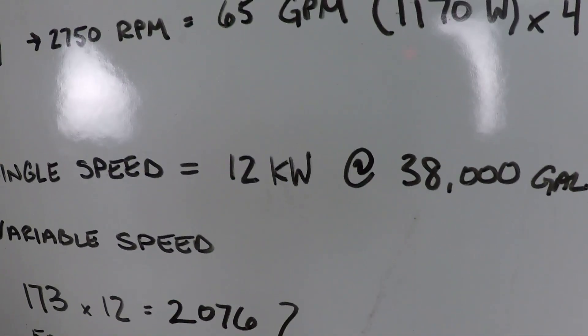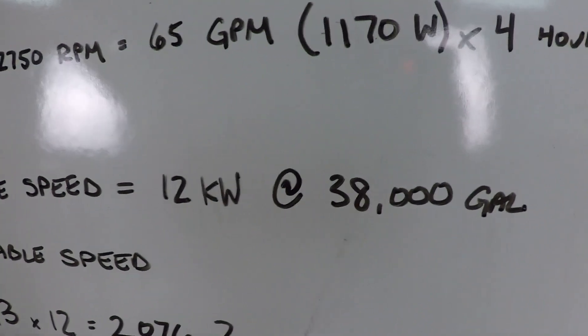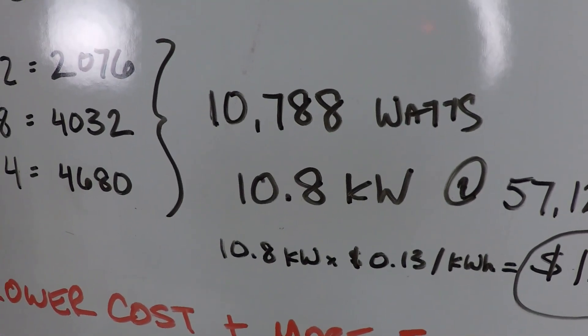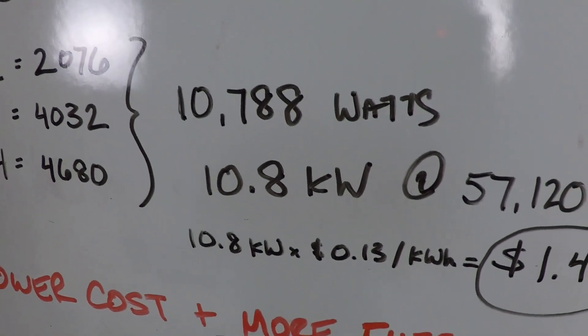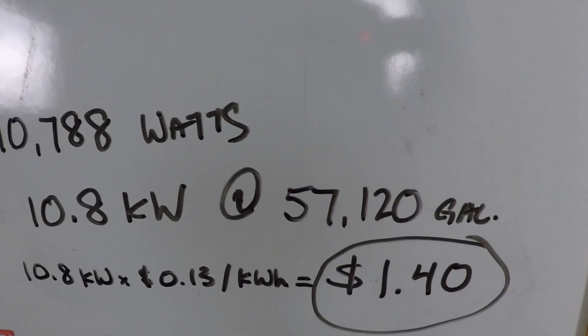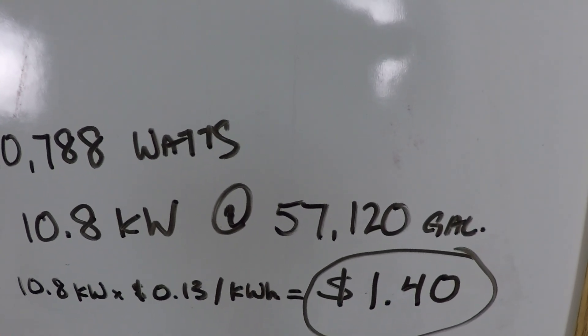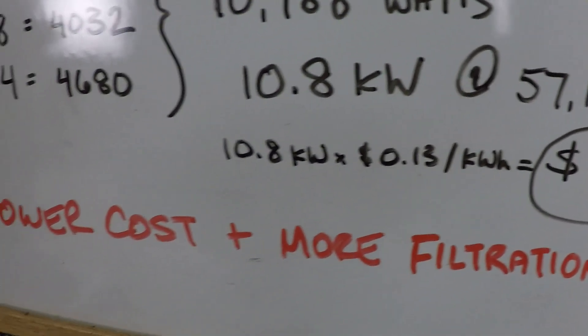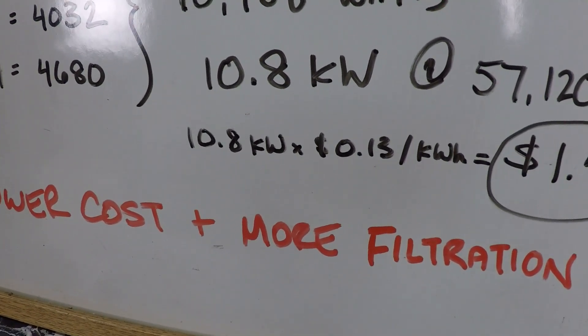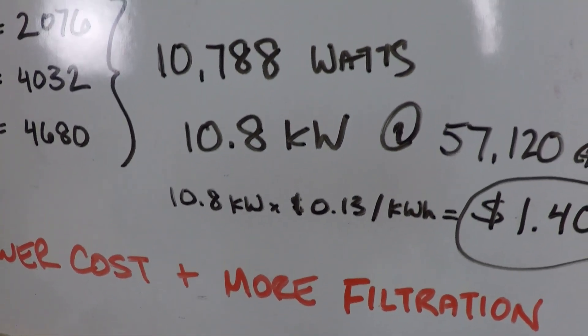There's your comparison right there. 12 kilowatts for 38,000 gallons of water versus 10.8 kilowatts, less power consumed, for 57,120 gallons of filtered water. Less power consumption, more filtered water, lower cost, more filtration. Seems like the answer is obvious. A definite win for variable speed pumps here.